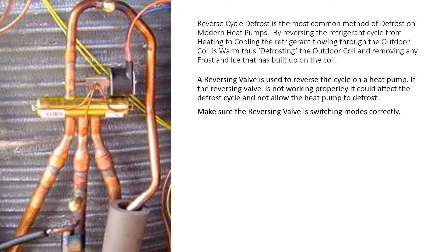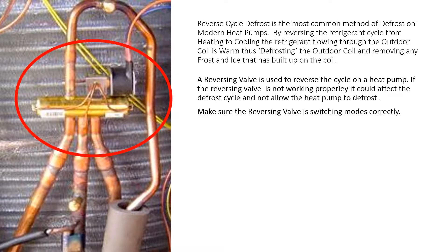Reverse cycle defrost is the most common method of defrost on modern heat pumps. By reversing the refrigerant cycle from heating to cooling, the refrigerant flowing through the outdoor coil is warm, thus defrosting the coil and removing any frost and ice buildup. A reversing valve is used to reverse the cycle. If the reversing valve is not working properly, it could affect the defrost cycle and not allow the heat pump to defrost, so make sure it is switching modes correctly.